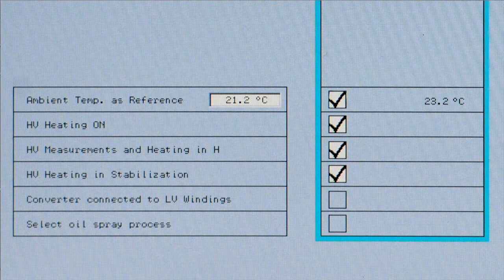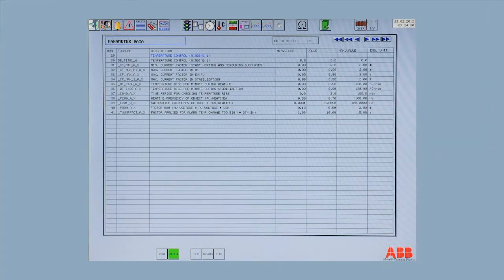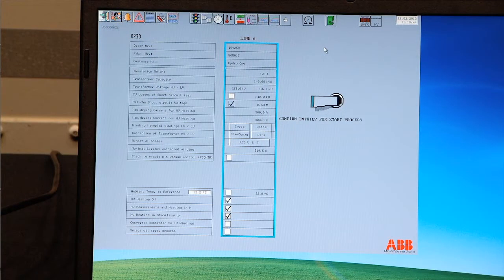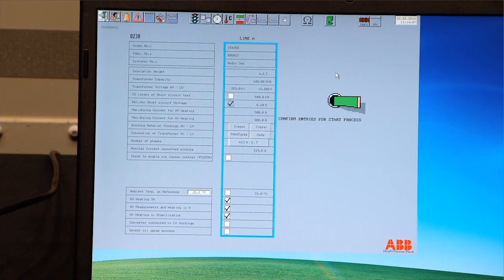It is recommended to use temperature sensors on the drying object as a reference, since the temperature in the container can deviate from the temperature of the transformer. During the process, some of the inputs can be altered by the operator, for example, maximum current. Parameters that cannot be changed during the process are disabled. After entering and rechecking that all necessary information for the transformer has been entered, the data has to be confirmed by switching the switch on the right side of the screen to the green color. A startup of the system is only possible after confirming the data.